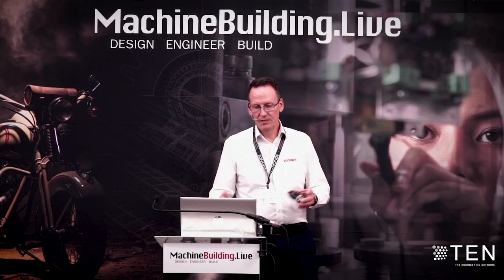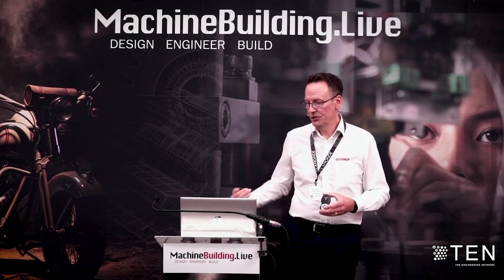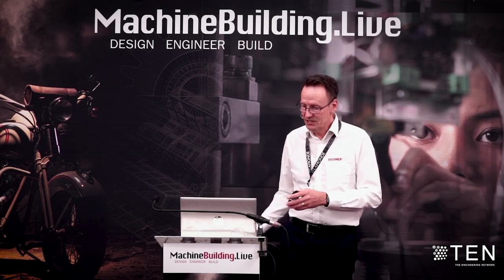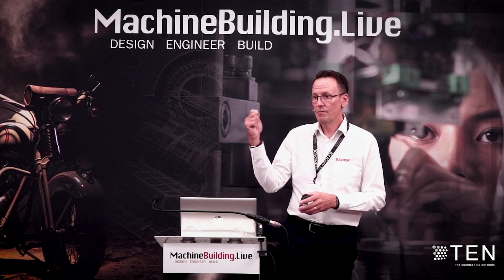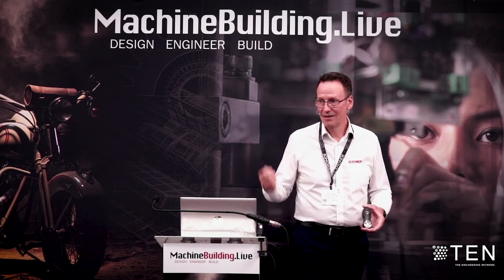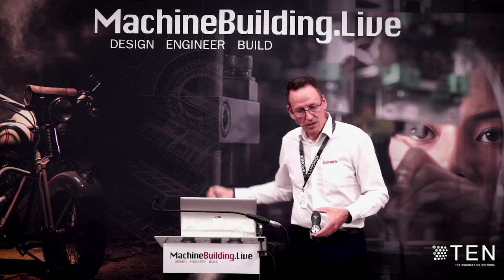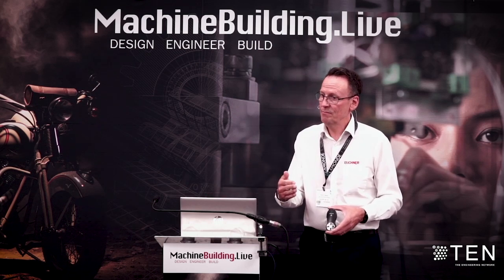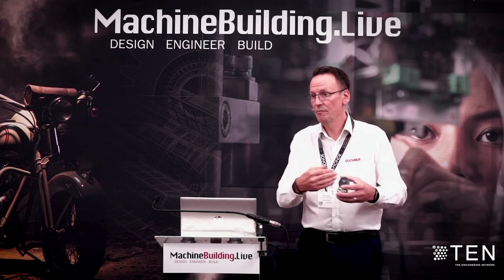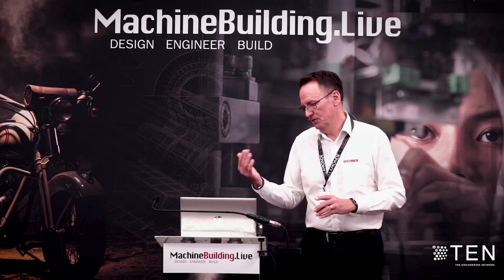Okay, so this particular system, the EN528 standard, describes that you should enter the aisle and you should lock it behind you. So on the back of the locking module or the handle module is a specific lock that locks behind, but it will only lock when the key is removed. So I'm in the aisle, I'm in the hazardous area, I've taken my RFID key from my main access point, the guard is locked behind me so no one else can pass through. At that point, there is open to manipulation because two people could go through in theory, but again, there's procedures in place wherever you go for stopping things like that happening.